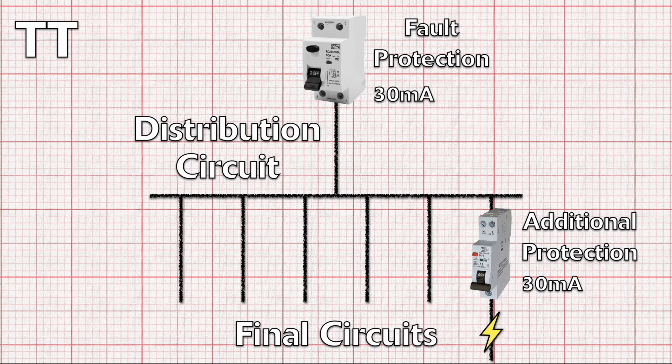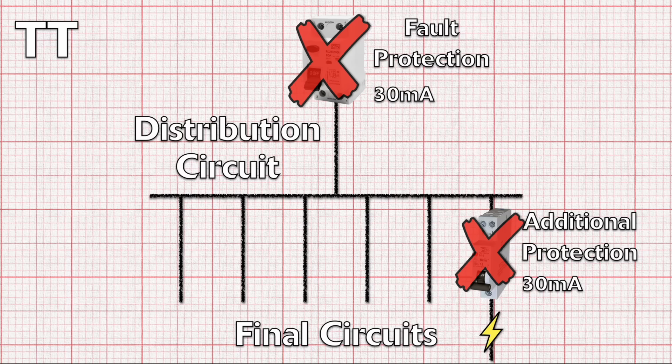An earth fault on the final circuit will cause the RCDs protecting the final circuit and the distribution circuit to trip at the same moment thus disconnecting healthy circuits. So what's the solution?